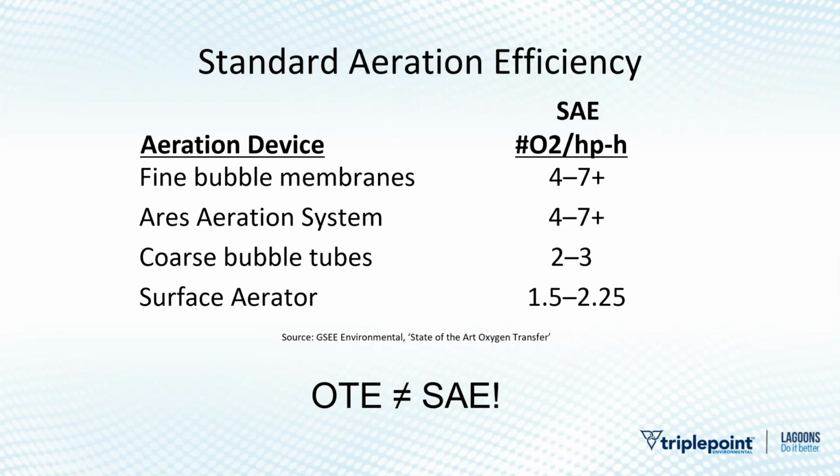And this goes to show what I was mentioning earlier: we're smashing together air and water. In general, it's just less energy intensive to be moving air around than it is to be moving water around. And the coarse bubble application, because it's less efficient, we have to transfer more air. And since we're transferring more air, there tends to be a lower SAE. So you can see the layout of the land here.